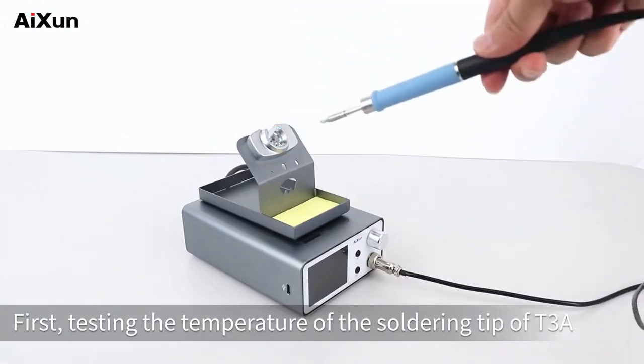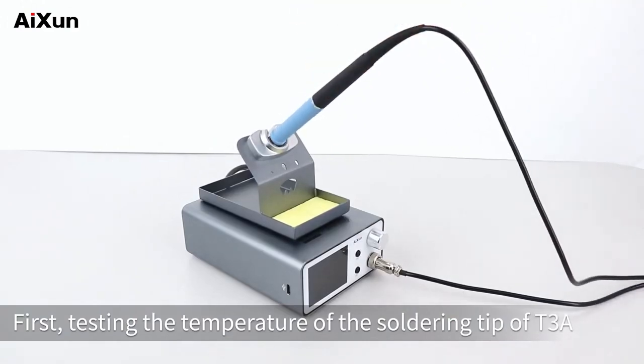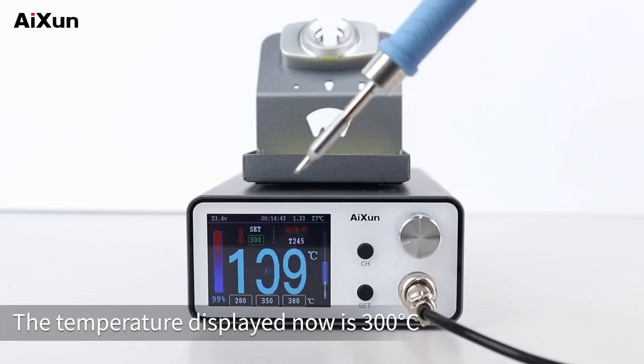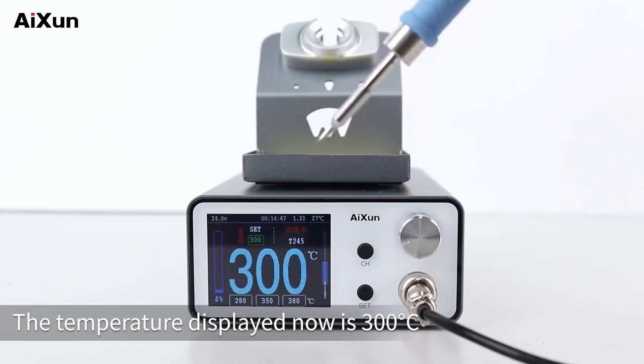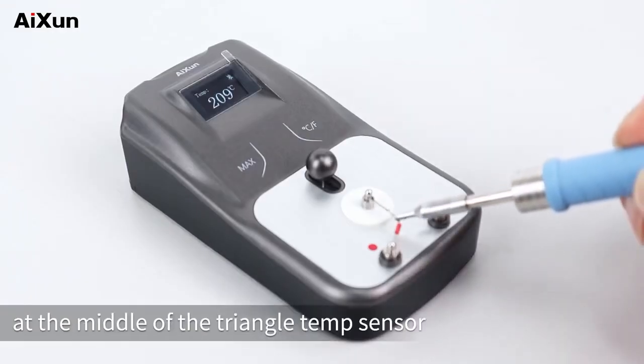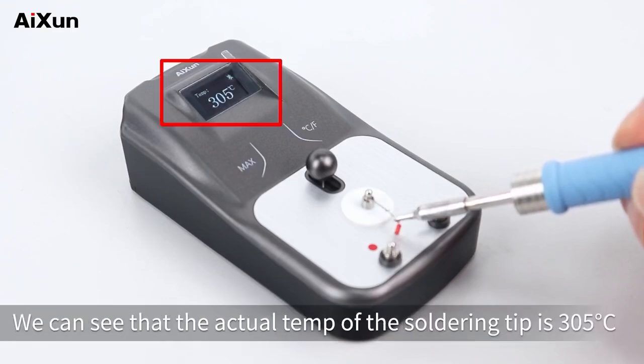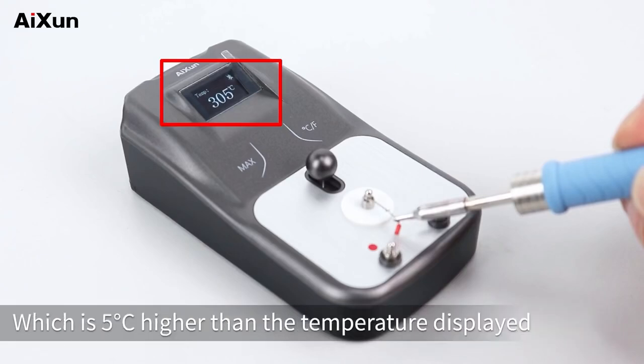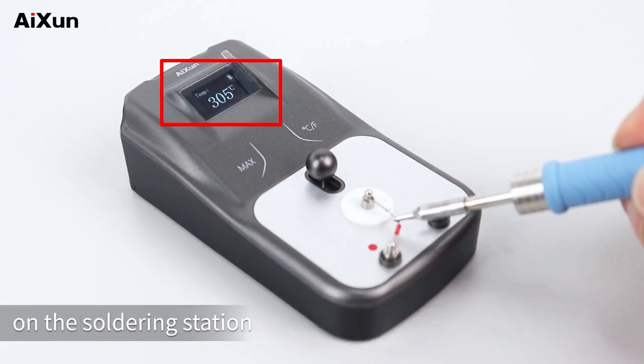First, testing the temperature of the soldering tip of T3A. The temperature displayed now is 300 degrees C. Then aiming the soldering tip at the middle of the triangle temp sensor, we can see that the actual temp of the soldering tip is 305 degrees C, which is 5 degrees Celsius higher than the temperature displayed on the soldering station.